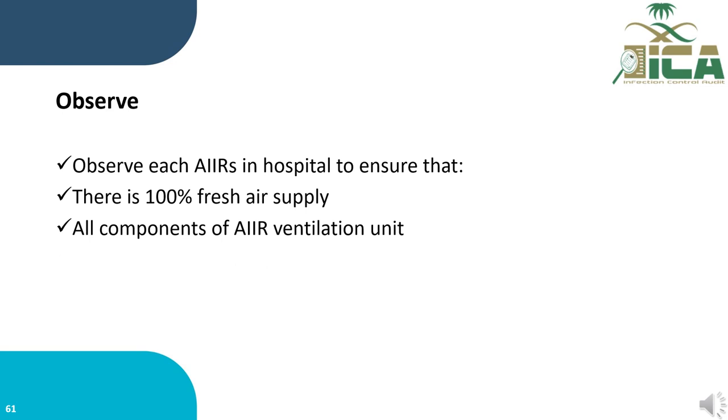You will observe each airborne infection isolation room in the hospital to ensure that there is 100% fresh air supply from central AC or a console separated unit, and that all the components of the airborne infection isolation ventilation unit, supply and exhaust, are connected to emergency power supply to maintain air pressurization in the event of power failure.